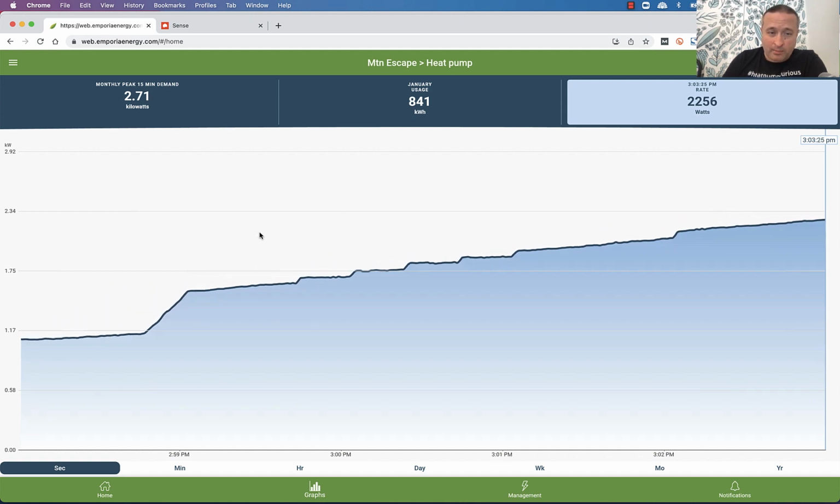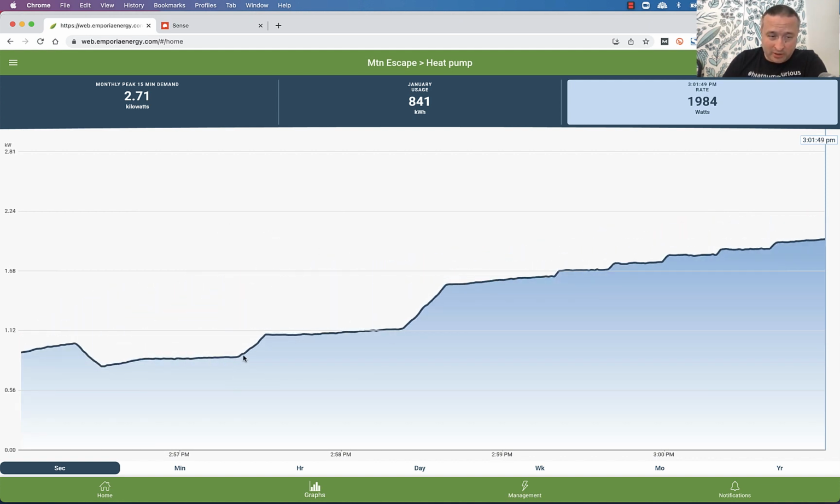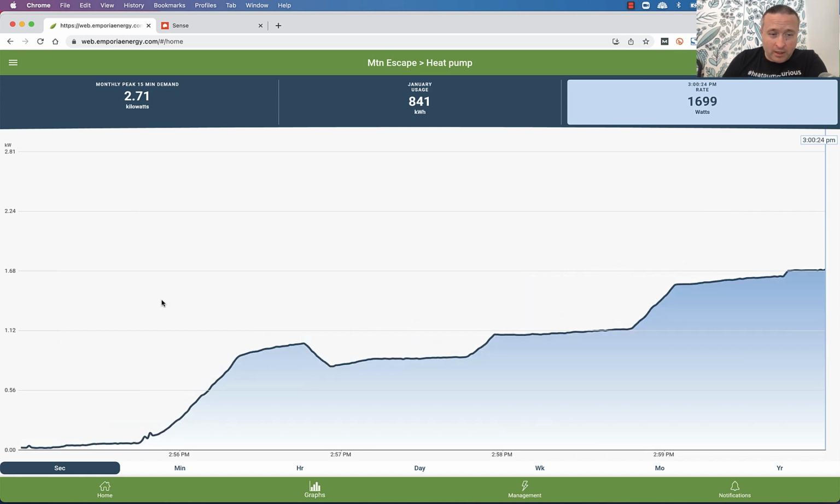And you can see it ramped up pretty gradually. You can see the jumps, like it did a couple of bigger jumps here. And it usually does this, it ramps up. It doesn't go super high, but notice that there's no spike. If you look at a single stage piece of equipment, when it turns on, you're going to get a huge spike, probably to about double what it pulls normally. So if it's a 3-ton system, which should pull 3000 watts when it's running, it may jump to 6000 for a second when it turns on, firing the compressor up.